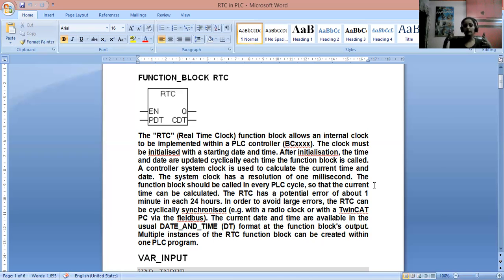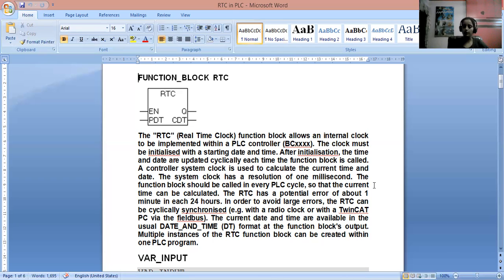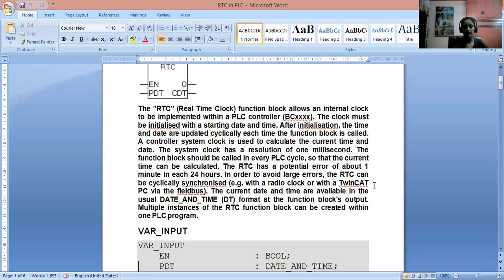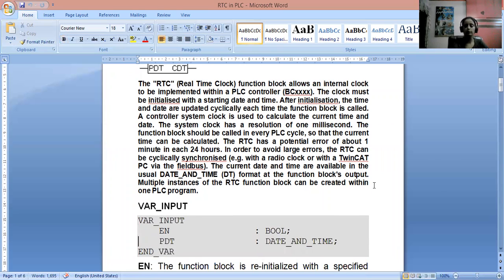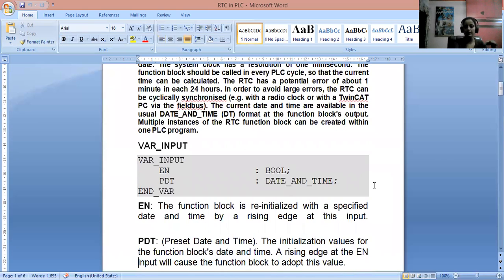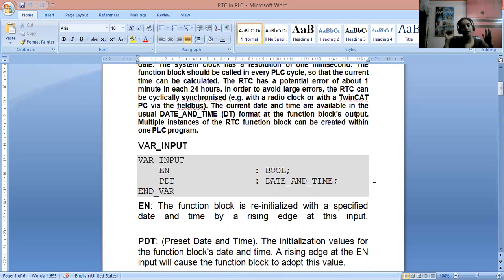The current date and time, usually in DT format, is available via the functional block. Multiple instances of the RTC function block can be created within one PLC program. EN is a BOOL input used to enable the function block. The RTC function block is re-initialized with a special date and time by the rising edge of this input — that is, false to true — which enables the function block.